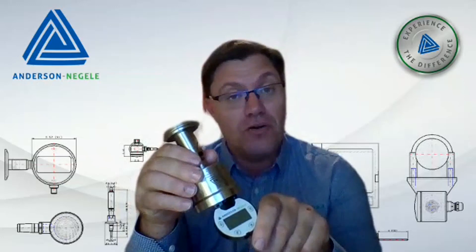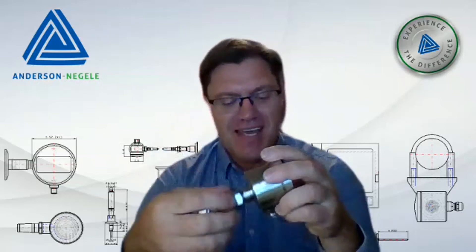It's a great product. One fun feature that I think was a happy accident, learned after the fact: for anyone with a flat-bottom tank with a sensor mounted on the bottom, the display on this device flips down. I've had the benefit during commissioning to take this display, flip it down, and with the sensor vertical, simply pull that display over and program from a difficult position under the bottom of a tank.